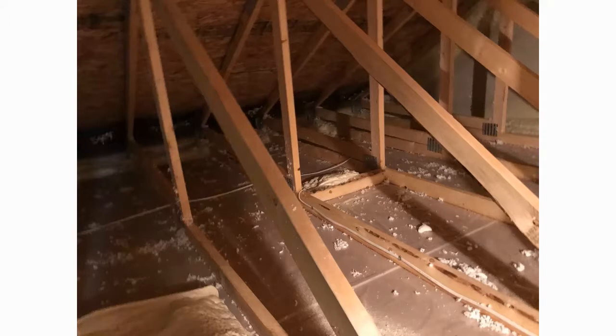But I think the ultimate, if you had an unlimited budget, you would likely do a hard ducted bathroom exhaust line, like maybe ABS or PVC pipe, run up to a gooseneck vent like I was showing. And then that would be encased in spray foam insulation. But now we're talking about probably a $1,000 bathroom exhaust fan pipe. And it's a non-starter. So what we're doing now is we'll use an insulated flex hose.